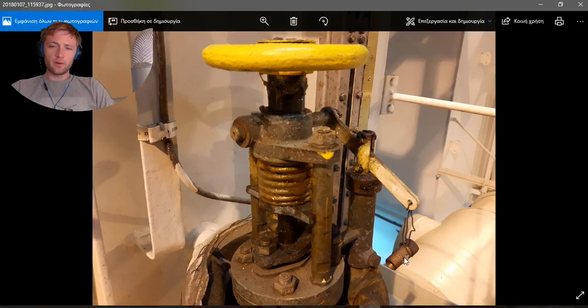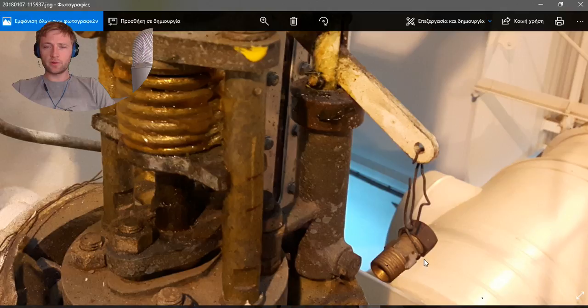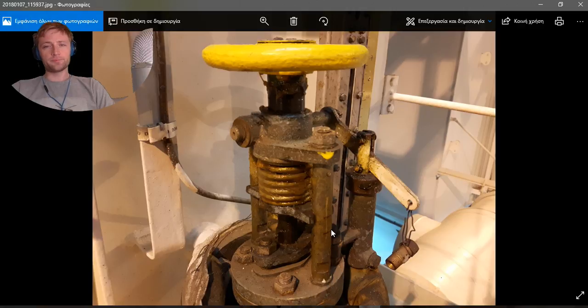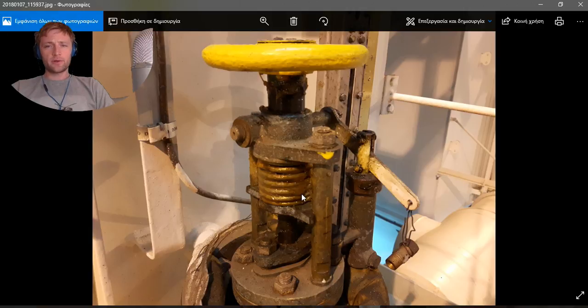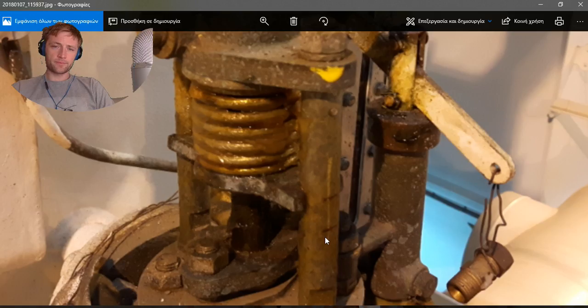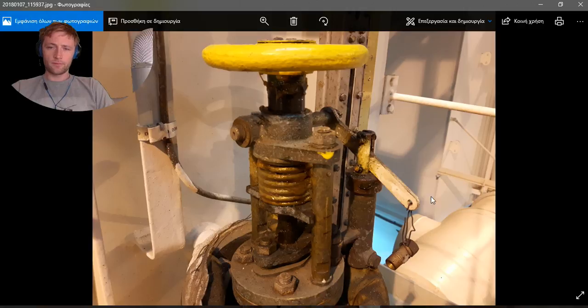All the pins and connections must be checked and safety pins must be in position. Here you can see an air connection point where you can connect to the piston and test this valve locally. Lubricate your shafts, springs, and connections, and also keep the indicator for open and close position as clean as possible.